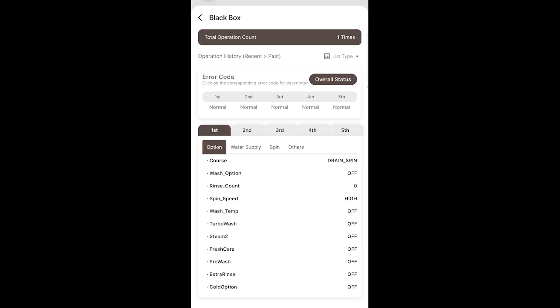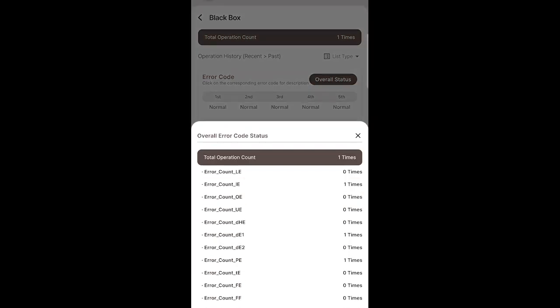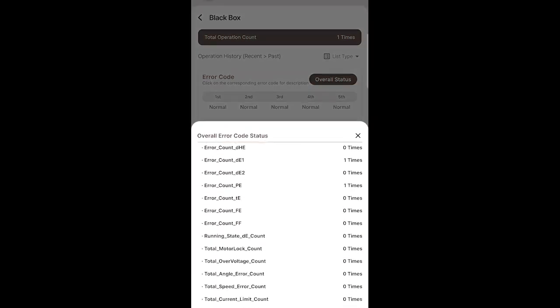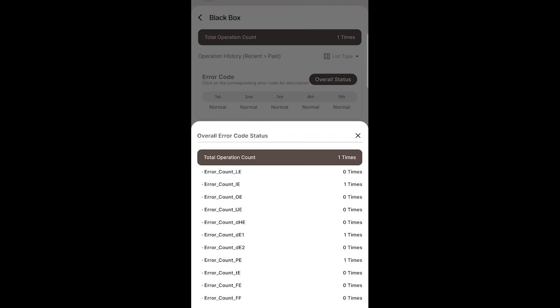If you select black box, it's going to give you some information from the last 5 cycles that the unit ran. So you can see here toward the top, you have an error code section, which gives you the last 5 cycles worth of codes. If you click overall status, it shows you all the error codes that can be displayed and how many times those have happened through the lifetime of the unit.